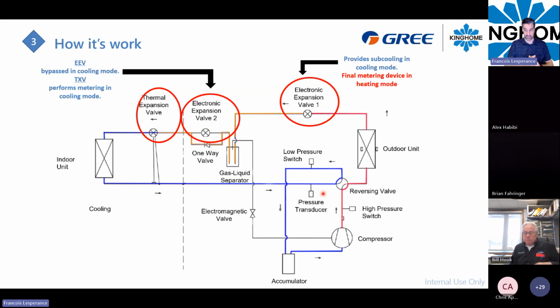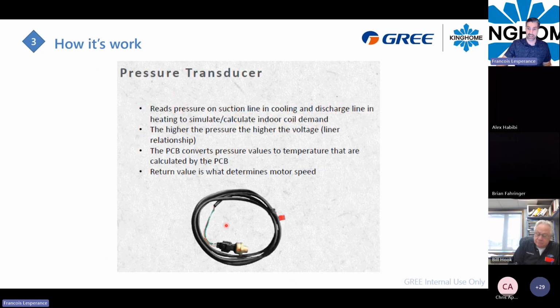So just remember that this compressor is an inverter compressor. It can fluctuate its frequency or its RPM. So by the capacity demand of the indoor unit, it will be translated here by the pressure transducer, and the compressor can go with a higher compression, or it can decrease its compression. So it's all managed by the pressure transducer right here.